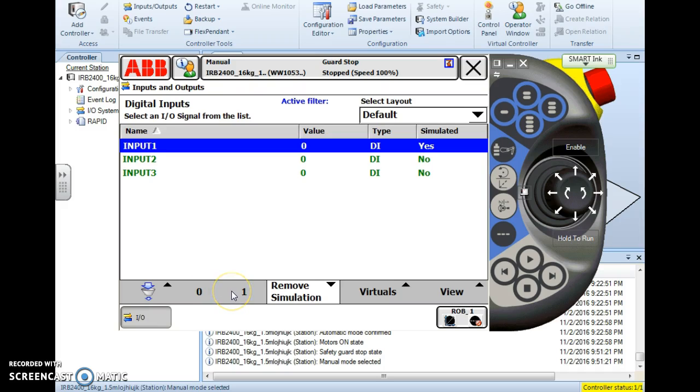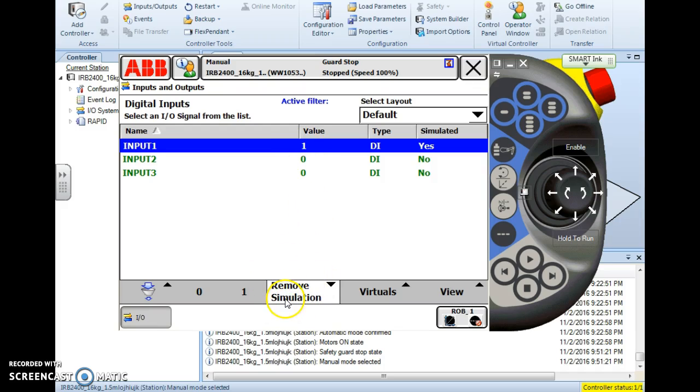Now important to remember about the simulation of inputs. If I simulate this input 1 or high or on, then this simulation will remain. A simulation does not go away unless I restore the system, do a b-start that takes me back before when the simulation was created if that's the case.